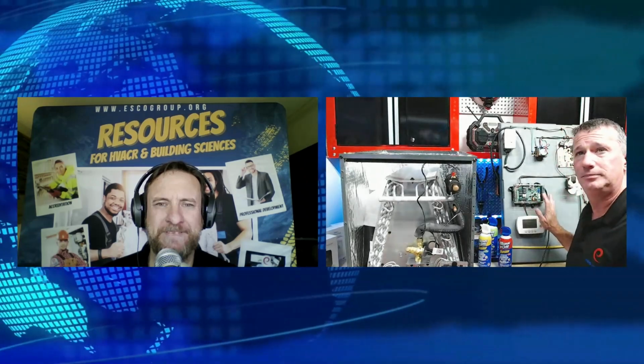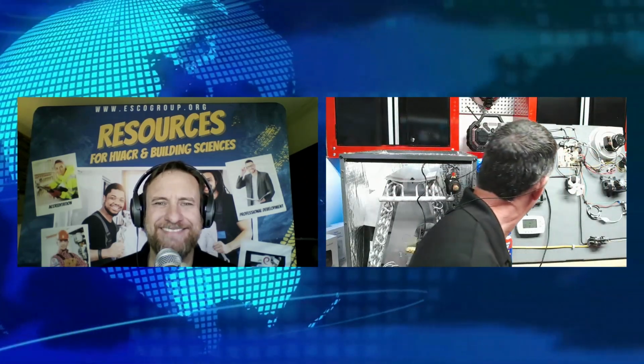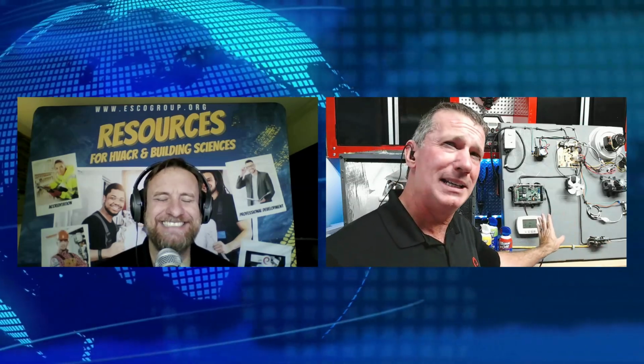This particular one here is called the Daikin Firefly. Dragonfly, I'm sorry. This is a dragonfly. So it's a Daikin Dragonfly, and it is an intermediate control board that goes exactly like we said, between our thermostat and our original indoor control board. Because this could have also been a retrofit system where I had a functional modern gas furnace with an ECM blower motor, not a PSC, and I am now wanting to put an A2L system on there that was an AHRI matchup. So what I can do is use our intermediate board in between the thermostat and our existing furnace's control board, and I can now do all of these sequences of mitigation for a piece of equipment.